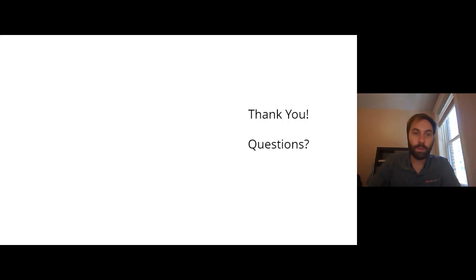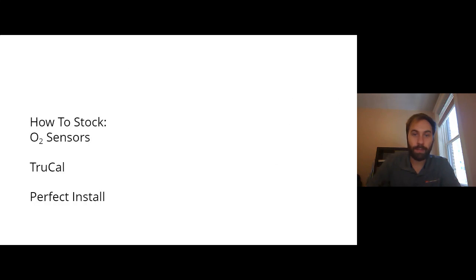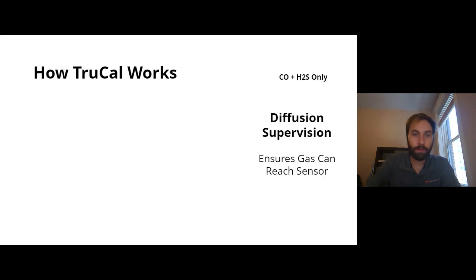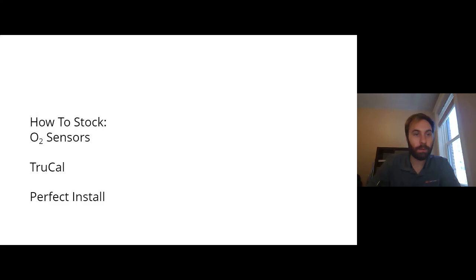How does the sensor, TruCal, indicate that it requires calibration? I'm going to go back to the TruCal slides. Jason, is there one in particular? We can just stay right there, actually. Right here? No, the one where we see the face of the transmitter. Oh, okay. This one. Yep. So when the TruCal says it needs to be calibrated, you see the sidebar lights of that Ultima X 5000 slowly pulse. They'll be on and off pulse, almost like a heartbeat, if you will. And that'll give a visual indication that it needs to be calibrated. If they can't be calibrated, will they stay green, or will they turn different colors? They will stay green.